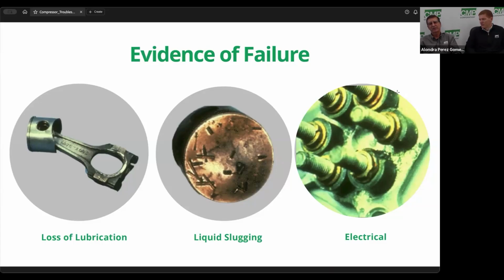But if it's got lack of lubrication to it, we can always tell by the scuffing of the pistons and the scalding on the rods and in the bearings. We can always tell there that's lack of lubrication there. Where that would be again a slow leak, a flood back instead of a slug there on it. I will tell you this, on a slug, if it breaks the valve plate on it, that head will become the hottest head. In other words, sometimes you have a compressor that has 3 heads on it, and one of them has already been discolored from the color of it. That is the head that has the problem under it, and you can do a valve plate job.